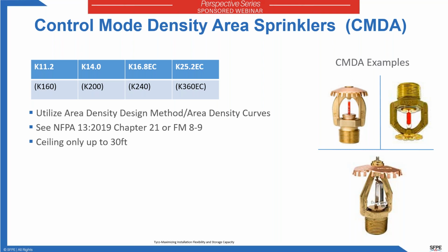Chapter 21 in the NFPA 13 2019 edition provides protection schemes for CMDA type sprinklers. FM 8-9 also has CMDA applications. Typically, depending on the commodity classification as well as the storage arrangement, CMDA can get ceiling-only protection up to about 30 feet. There are examples of CMDA sprinklers: 11 K factor sprinklers, 14 K factor sprinklers, 16.8 uprights and pendants, and a K25 extended coverage upright sprinkler. There's also a pendant that can be used as CMDA sprinklers per NFPA 13.